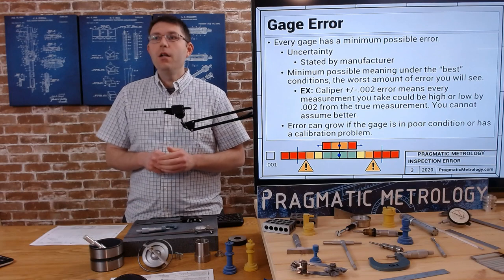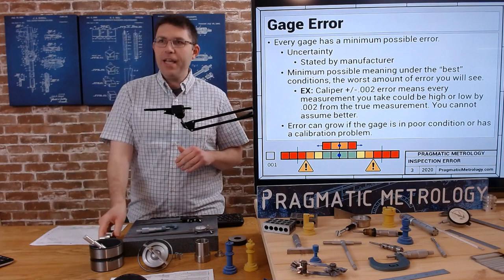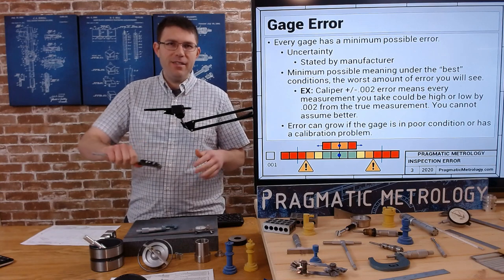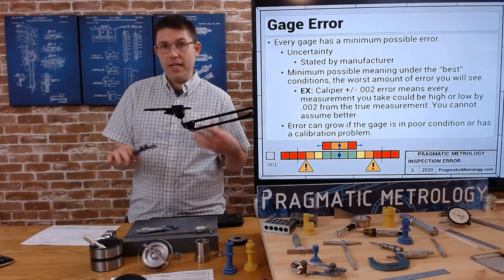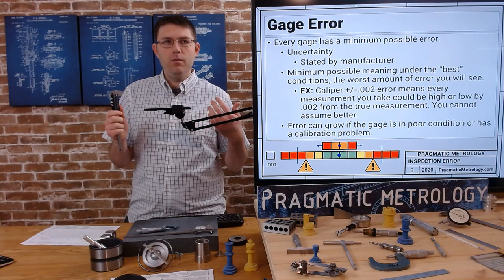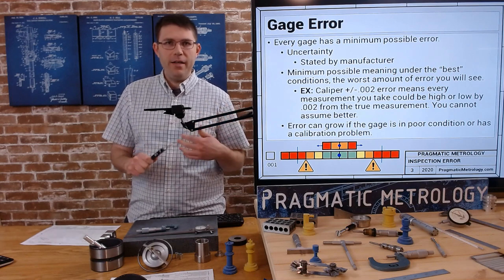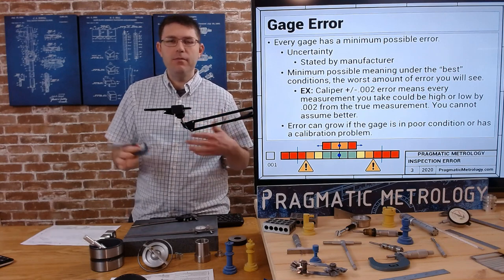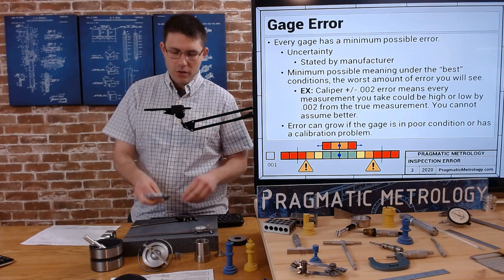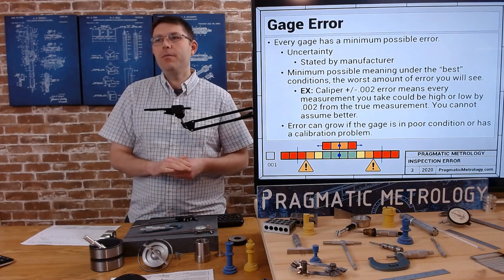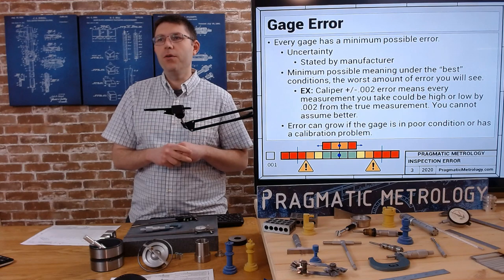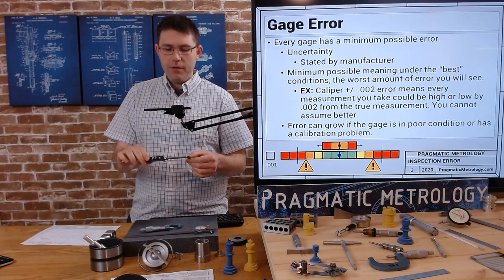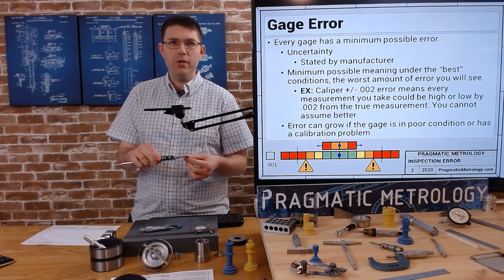Every gauge has a minimum possible error. With a caliper, every reading you take is basically plus or minus 1 thousandth or plus or minus 2 thousandths. That's the accepted accuracy of a caliper. With a micrometer, it's plus or minus 1 thousandth. Those numbers vary based on manufacturer and size of the gauge. The minimum possible means under the best conditions, the worst amount of error you will see. You could see more error than plus or minus 1 with a caliper if you have bad technique or a gauge in poor condition, but you're not going to see better than that.